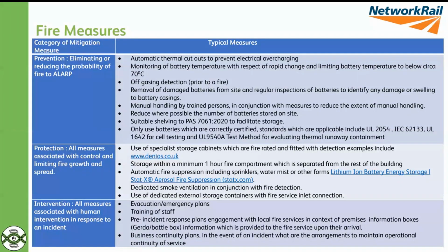PPI stands for prevention, because our best line of defense is preventing fires in the first place, recognizing that you can't eliminate that to zero — so it's about reducing the probability to as low as reasonably practical. Then protection, which isn't one size fits all because it depends on infrastructure arrangements and building configuration. And intervention, the human bit, in terms of emergency procedures and pre-incident response plans with the fire services.